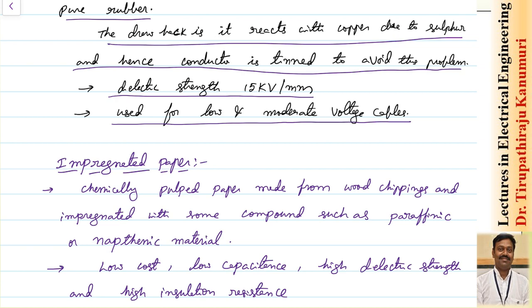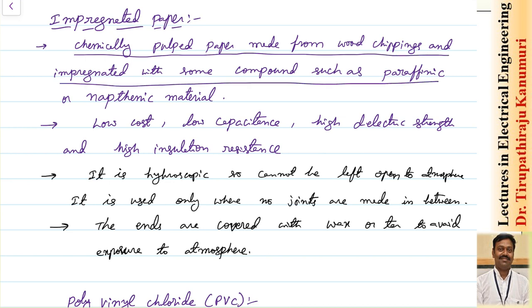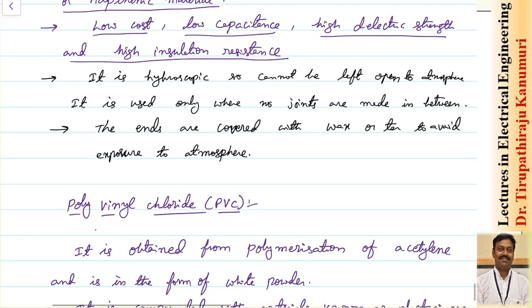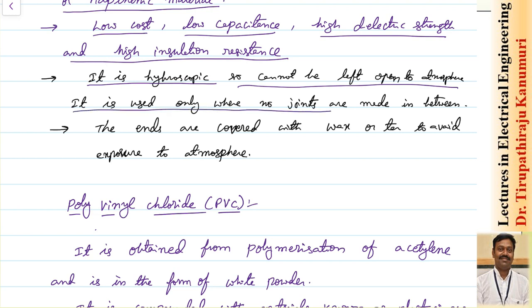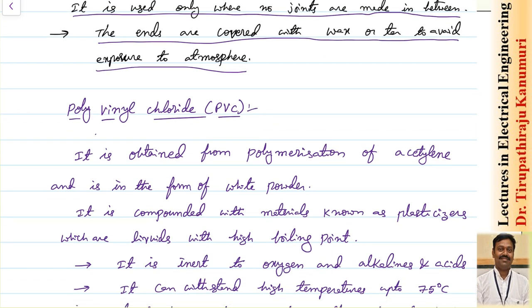Impregnated paper is the most commonly used cable insulating material. It is chemically pulped paper made from wood chippings and impregnated with compounds such as paraffin and naphthenic materials. Its advantages are low cost, low capacitance, high dielectric strength, and high insulation resistance. However, it is hygroscopic — it easily absorbs moisture, drastically reducing dielectric strength. Therefore, it cannot be left open to the atmosphere, no joints should be made mid-cable, and wherever the ends are cut they must be covered with wax or tar to prevent atmospheric exposure.